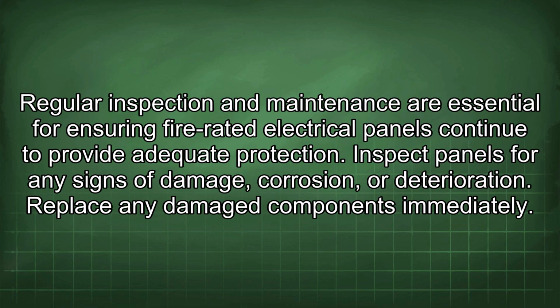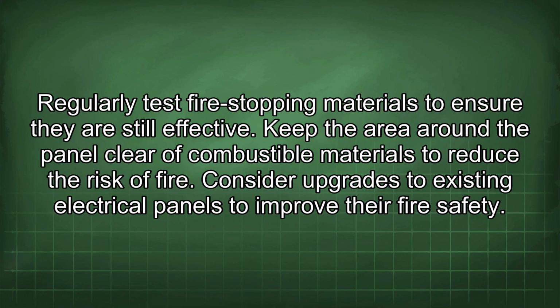Regular inspection and maintenance are essential for ensuring fire-rated electrical panels continue to provide adequate protection. Inspect panels for any signs of damage, corrosion, or deterioration. Replace any damaged components immediately. Regularly test fire-stopping materials to ensure they are still effective. Keep the area around the panel clear of combustible materials to reduce the risk of fire.